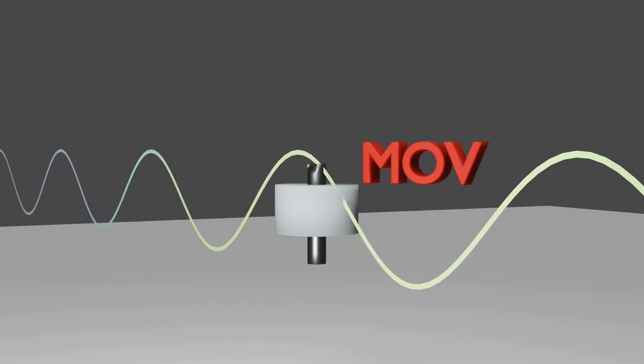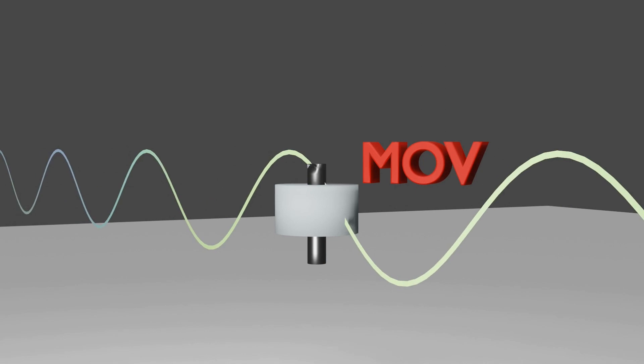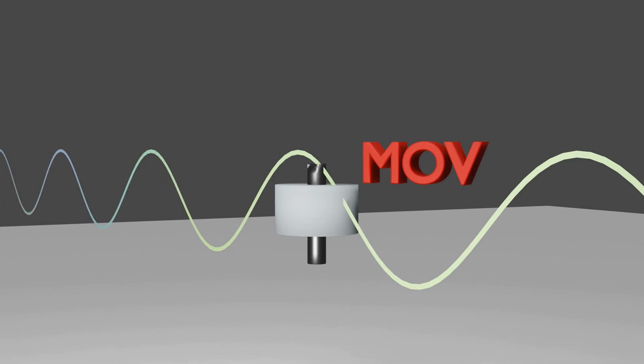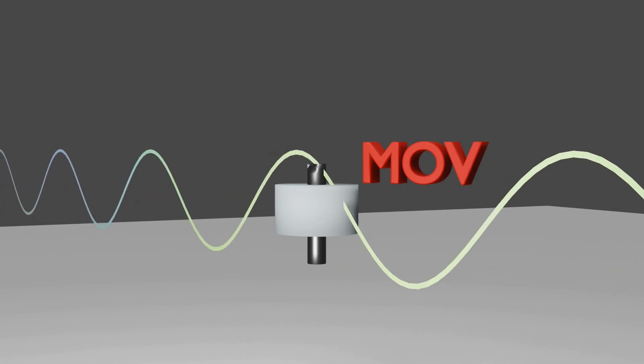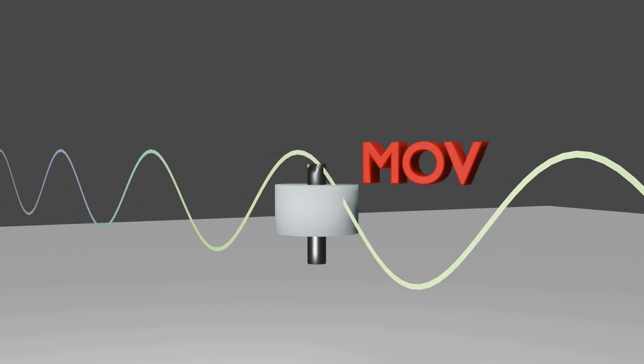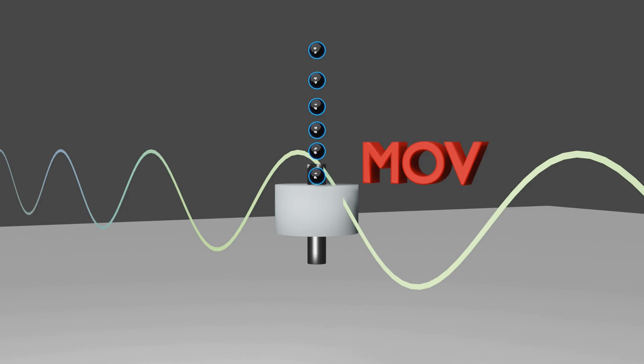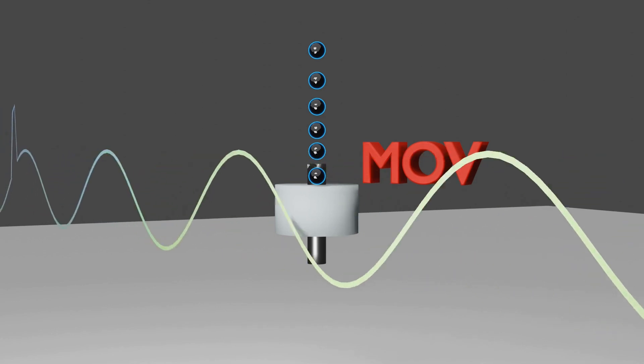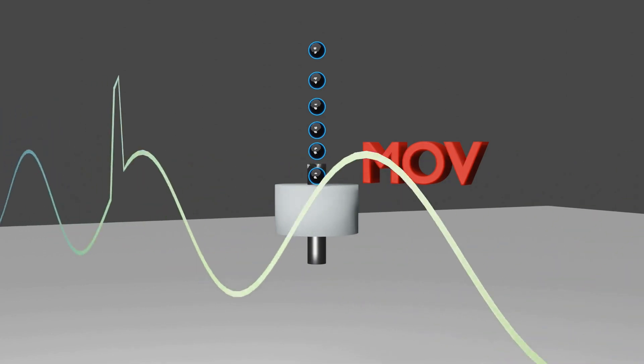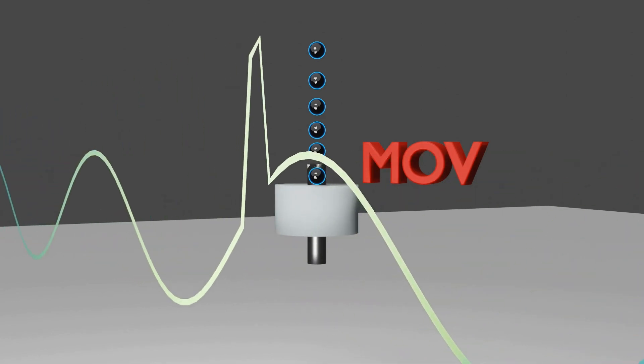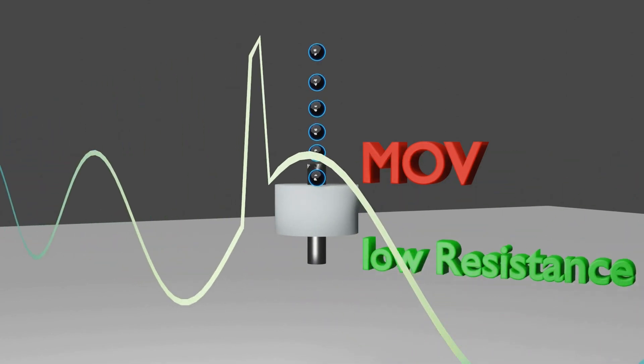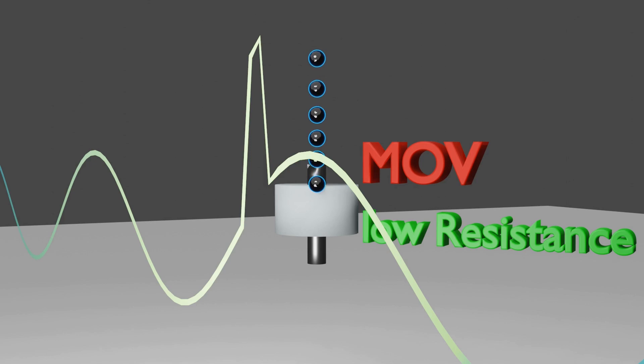...if this MOV Block is meant for an 11KV system and 11KV voltage comes across this block, it provides high resistance so that no current passes through this block. But if suddenly voltage spike or surge comes across the block, then it provides low resistance and allows current to pass from it.